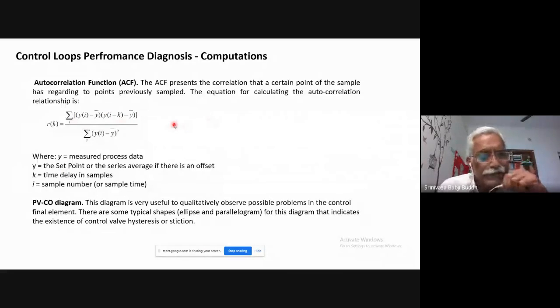Then another one is this PV and CO diagram. That means process variable and control output diagram. Typically if the diagram has some sort of parallelogram or ellipse shape when we plot the control output against the process variable, it gives an indication of the presence of stickiness in the control valve, hysteresis. Okay. So like this, we do various computations. You can see that we are doing a lot of data crunching based on this process data that is collected from the control systems and carry out all these computations in the data analytics system. Okay. There are a lot of other indices also. I'm not covering all of them.